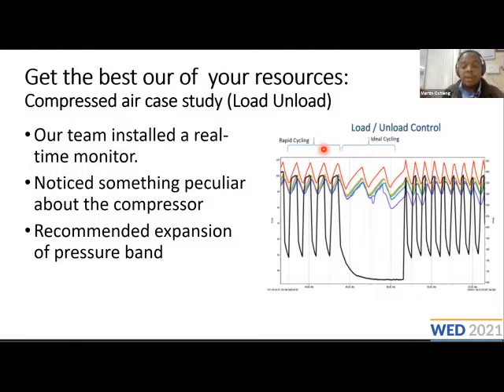It was between 6.5 and 7 bar, basically a difference of 0.5 bar, making it so that whenever it reaches 6.5 bar, the compressor loads up to this particular point here, where it reaches 7 bar. But once it does that, as it's unloading, it only unloads up to this particular point. At this point, it would have reached 6.5 bar, making it so that the energy consumption was a little bit higher than expected. So we recommended that the team on the ground expand that pressure band slightly and monitor the effects on the machines.